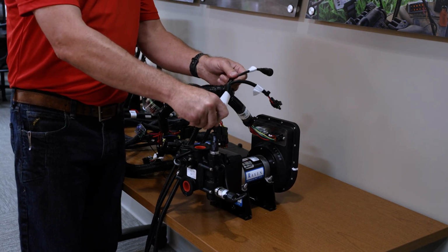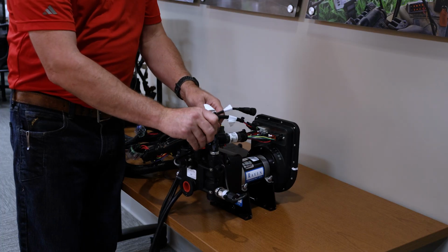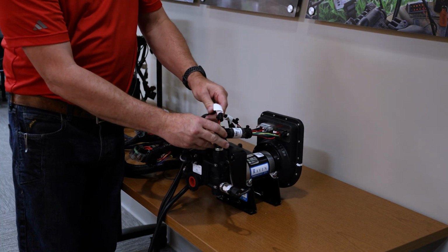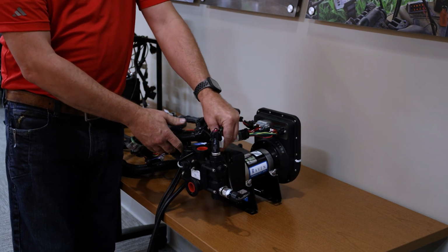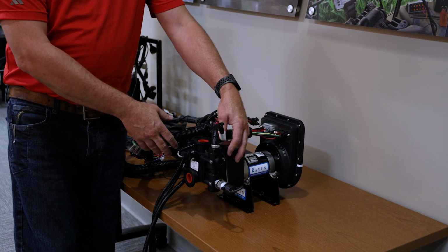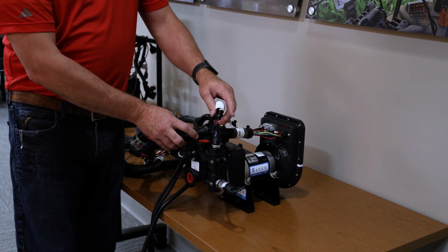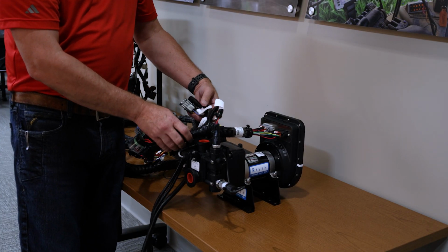The round connector with the purple gasket is your pressure transducer. One thing I'll tell you from experience is you do not want this harness pulling down on the pressure transducer—you will ruin the harness. So we do want a little bit of slack going into the pressure transducer.